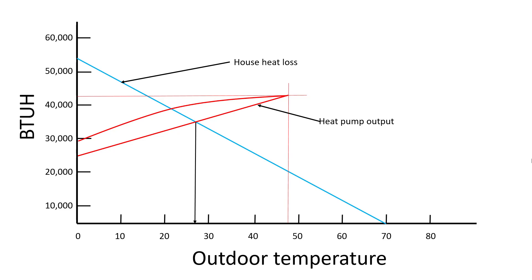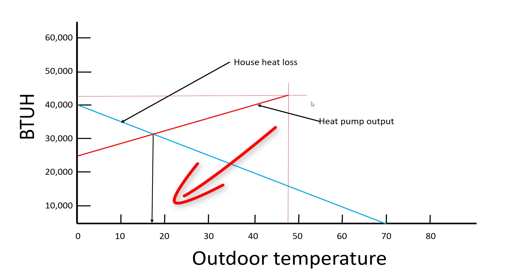It would change if the house is tighter, better insulated, there's less heat loss. Those numbers would change. The heat loss for the house would look more like this where we're only losing say about 31 or 32,000 BTUs at 20 degrees. Then our balance point shifts down.